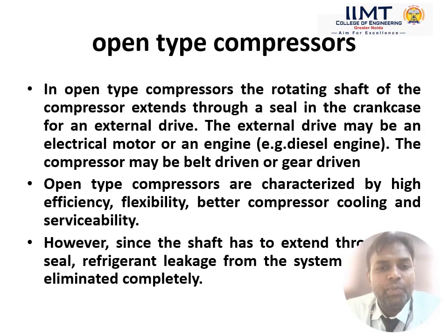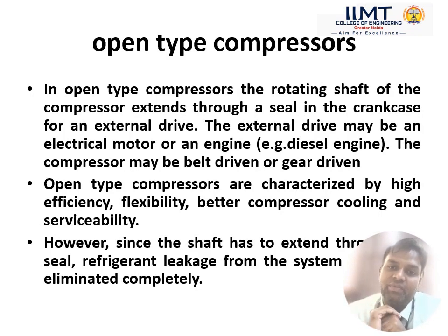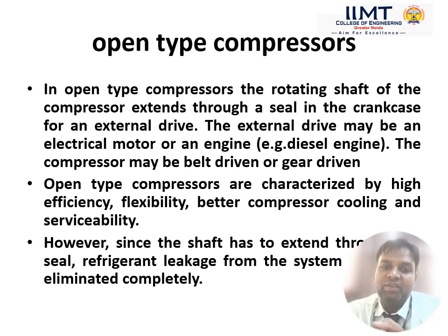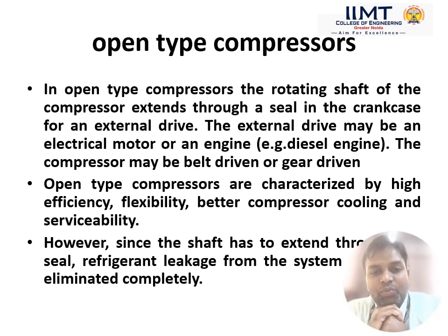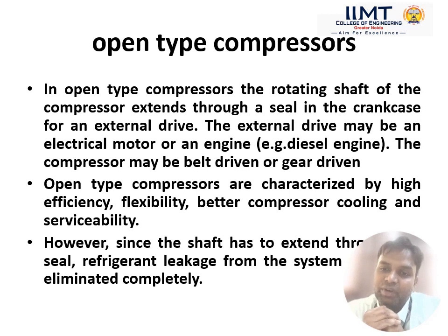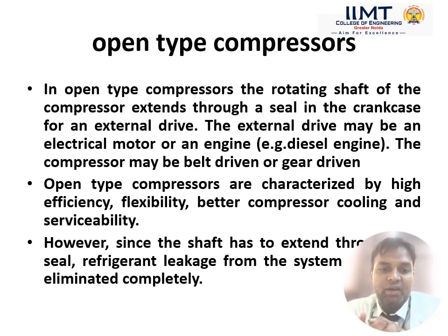In an open type compressor, the rotating shaft of the compressor extends through a seal in the crankcase for an external drive. The external drive may be an electrical motor or engine, and the compressor may be belt-driven or gear-driven. Open type compressors are characterized by high efficiency, flexibility, better compressor cooling, and suitability for serviceability. However, a disadvantage is that refrigerant leakage from the system cannot be completely eliminated.